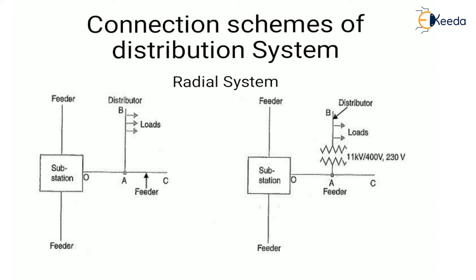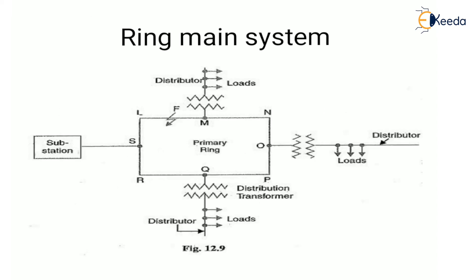The radial system has a disadvantage: if any fault occurs on the feeder or distributor, it cuts off the supply to the consumer, so this system is used for short distances only. Next is the ring main system — a loop circuit starts from the substation bus bar, makes a loop through the areas to be served, and returns to the substation. Distributors are tapped from different points such as M, O, and Q.